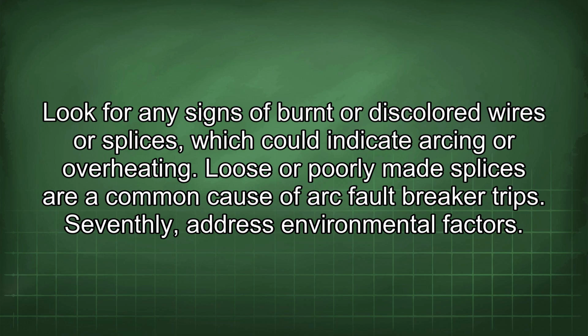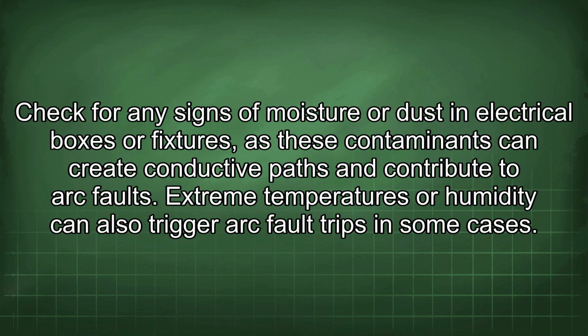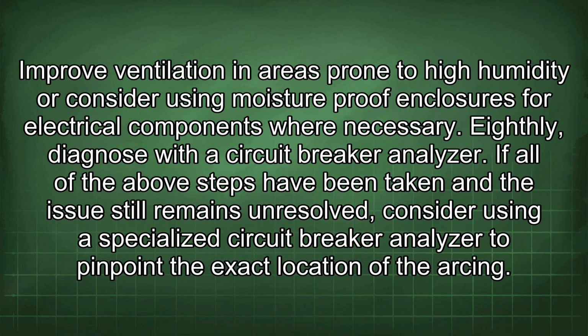Seventhly, address environmental factors. Check for any signs of moisture or dust in electrical boxes or fixtures, as these contaminants can create conductive paths and contribute to arc faults. Extreme temperatures or humidity can also trigger arc fault trips in some cases. Improve ventilation in areas prone to high humidity or consider using moisture-proof enclosures for electrical components where necessary.